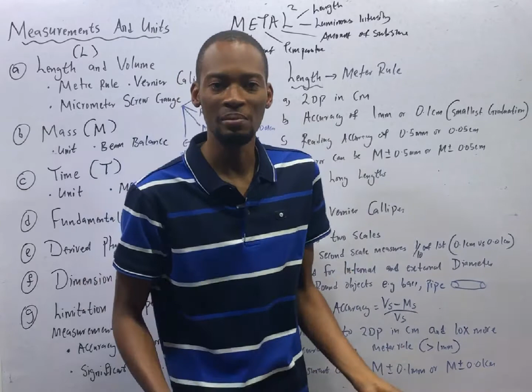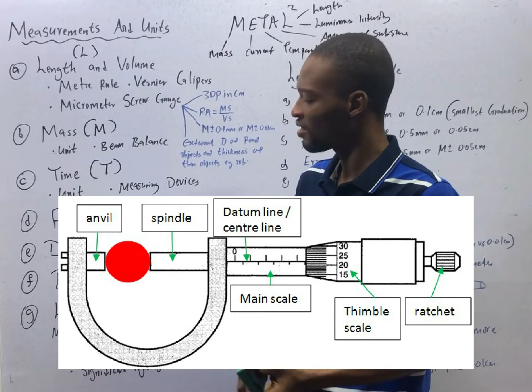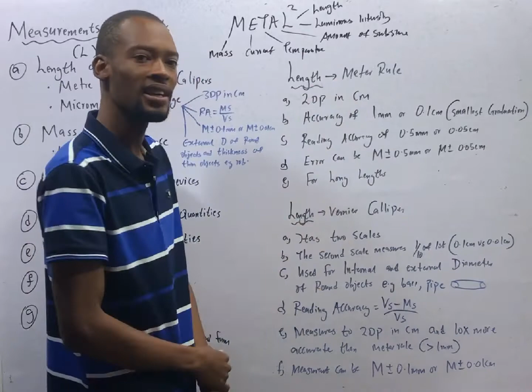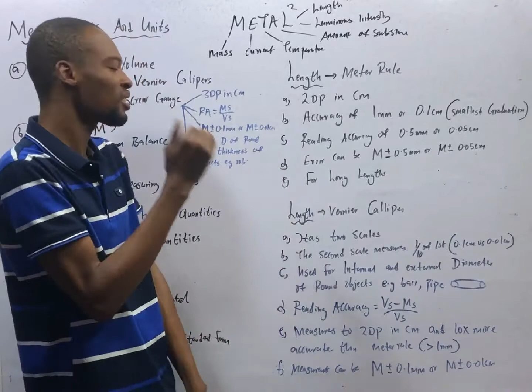Then micrometer screw gauge, on the other hand, is also an instrument used for measuring length. It measures to 3 decimal places in centimeter. This is what differentiates it from the meter rule and the vernier caliper. These two measure to 2 decimal places in centimeter, but micrometer screw gauge measures up to 3 decimal places in centimeter. And the accuracy of micrometer screw gauge is the main scale divided by vernier scale reading, which means it also has 2 scales like the caliper. Therefore, the similarity between caliper and screw gauge is that they have 2 scales.